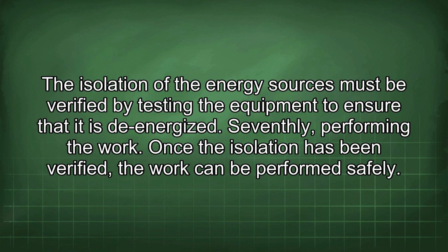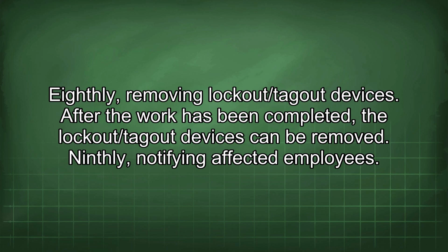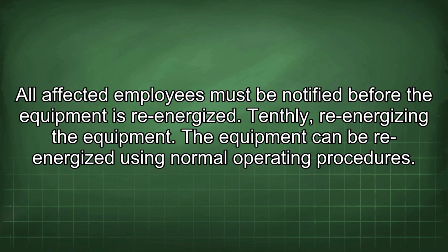Seventhly, performing the work. Once the isolation has been verified, the work can be performed safely. Eighthly, removing lockout/tagout devices. After the work has been completed, the lockout/tagout devices can be removed. Ninthly, notifying affected employees. All affected employees must be notified before the equipment is re-energized. Tenthly, re-energizing the equipment. The equipment can be re-energized using normal operating procedures.